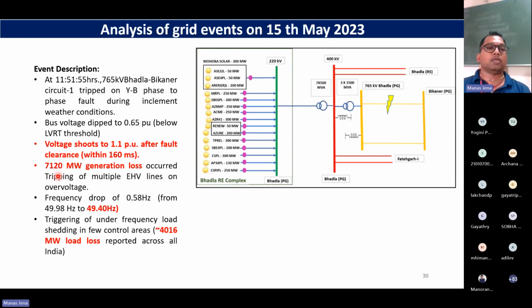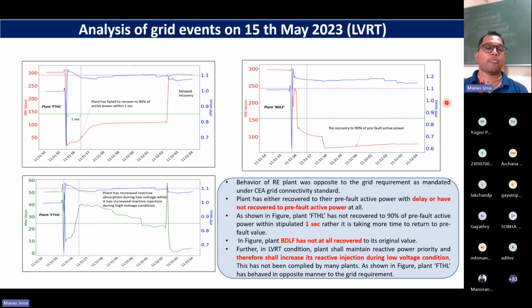Similarly here also, close to 7,000 megawatt of generation was lost on over voltage. If you lose this much generation, frequency dropped to as low as 49.4, which actually triggered our under frequency load shedding scheme, and because of the under frequency load shedding, close to 4,000 megawatt of load was lost. You can see, a very conventional event, but close to 7,000 of generation loss and close to 4,000 of load loss. So what happened actually? Let us try to dig into this.